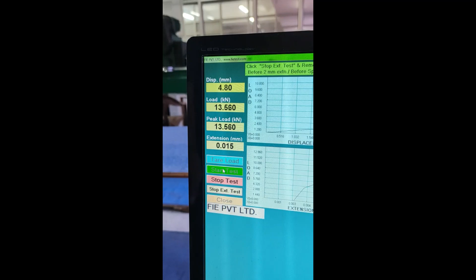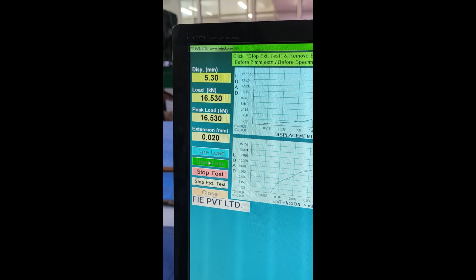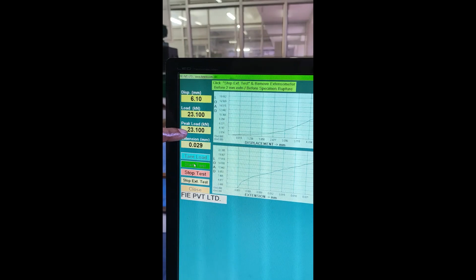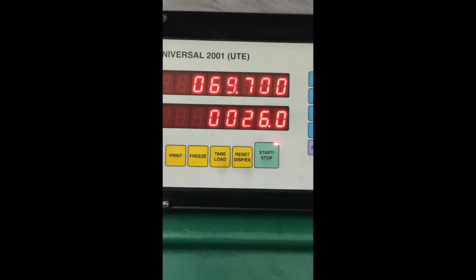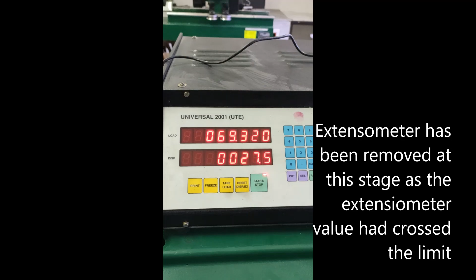Once the test completes, then this graph will be completely and clearly visible to you. So these are the online values. The values are increasing instantaneously, so the readings will go on increasing. This is the extensometer value, this is the peak load, this is the load going on, and this is the displacement. The load goes on increasing, and now it is showing the displacement from the linear encoder. Necking is about to happen. Now you see, necking will happen.